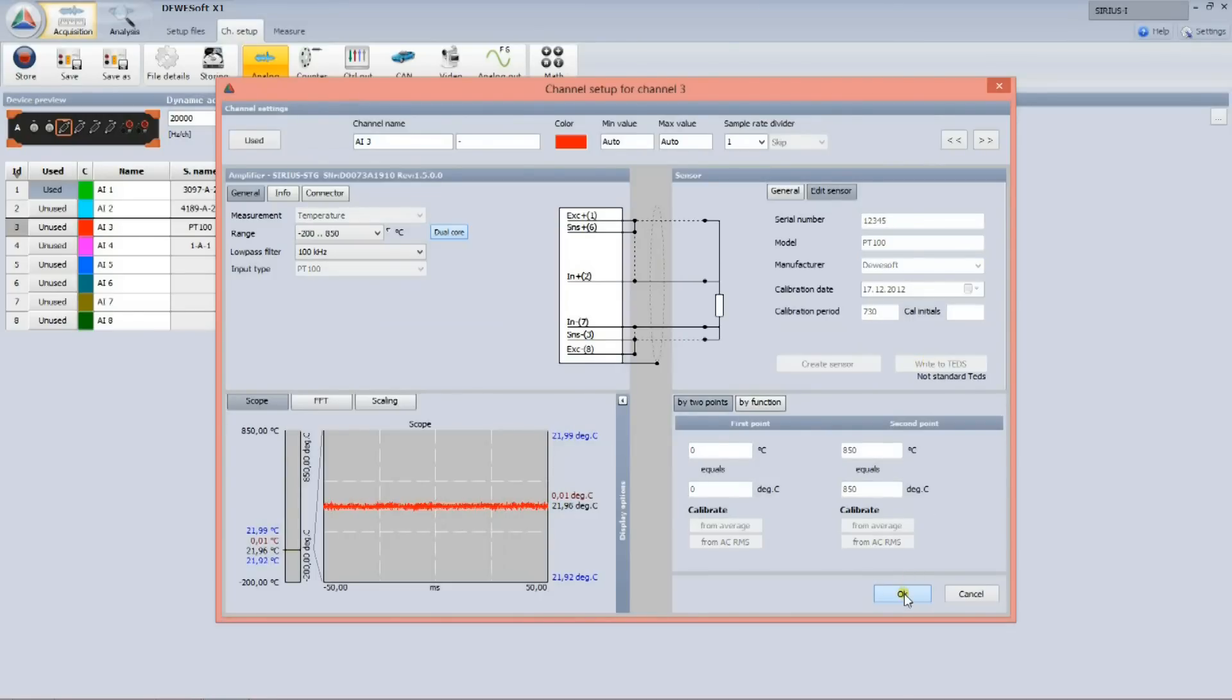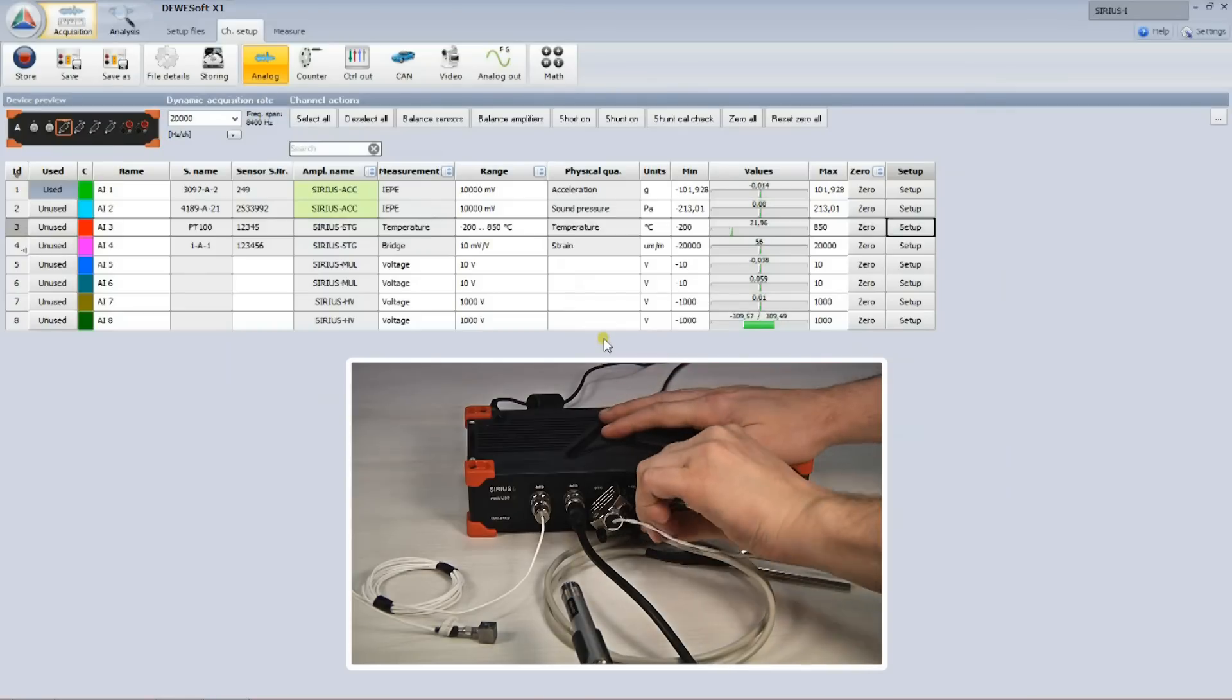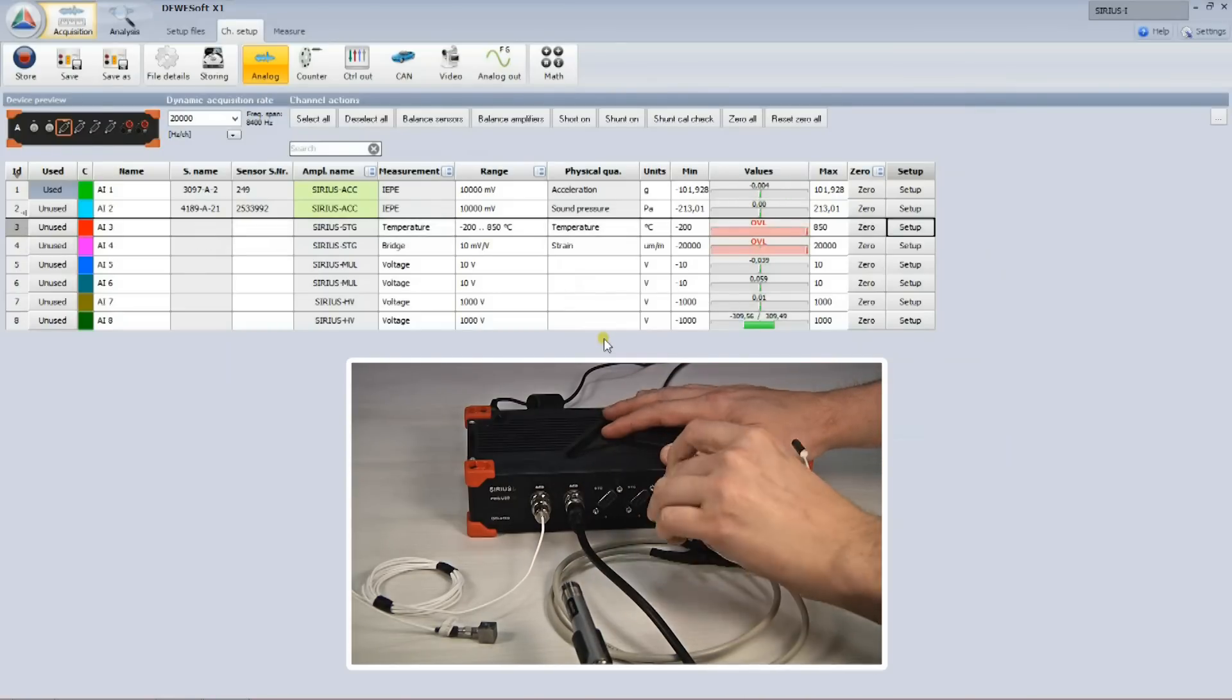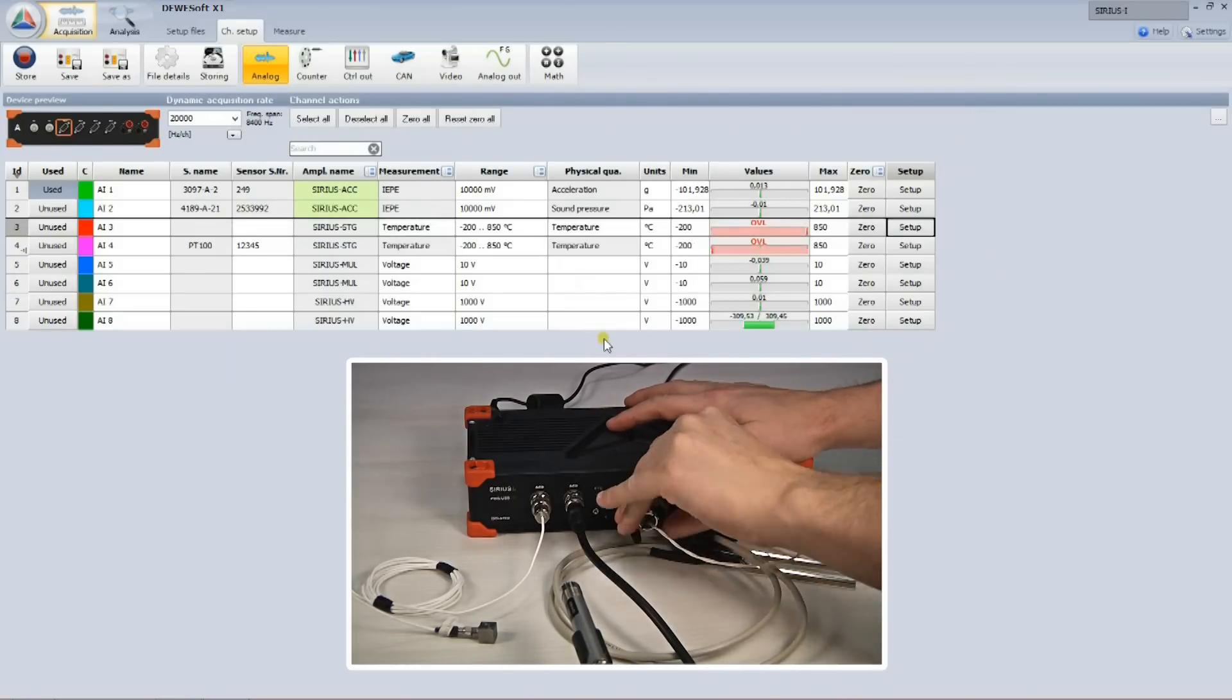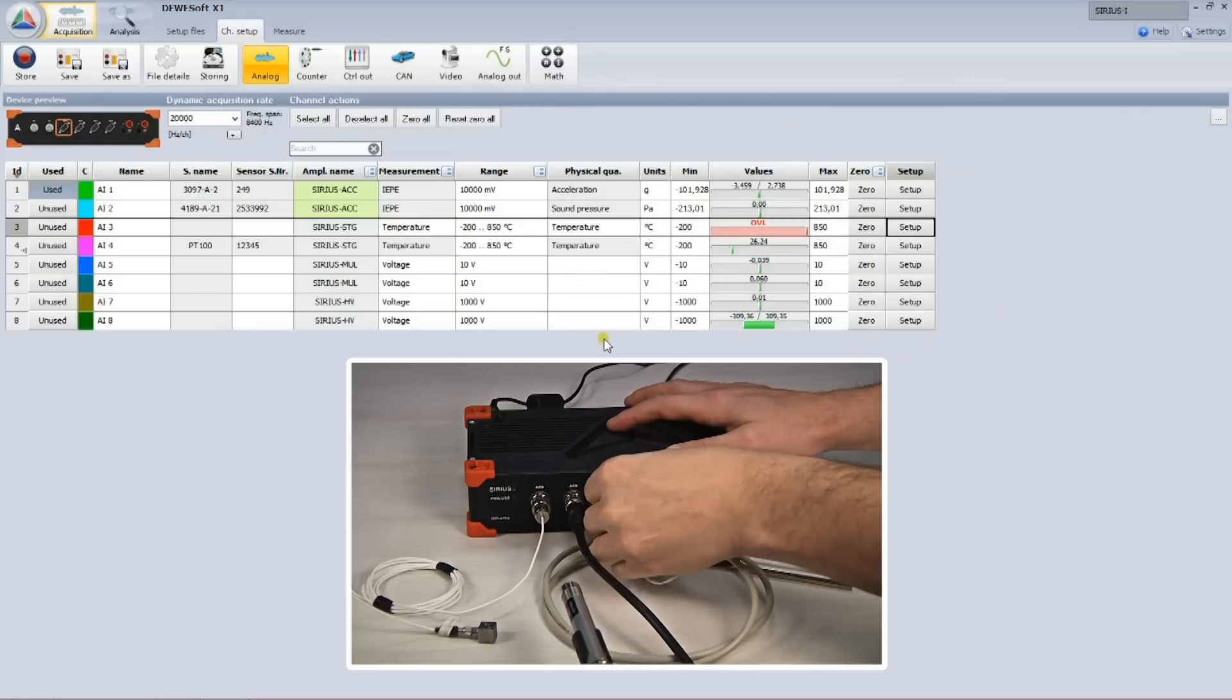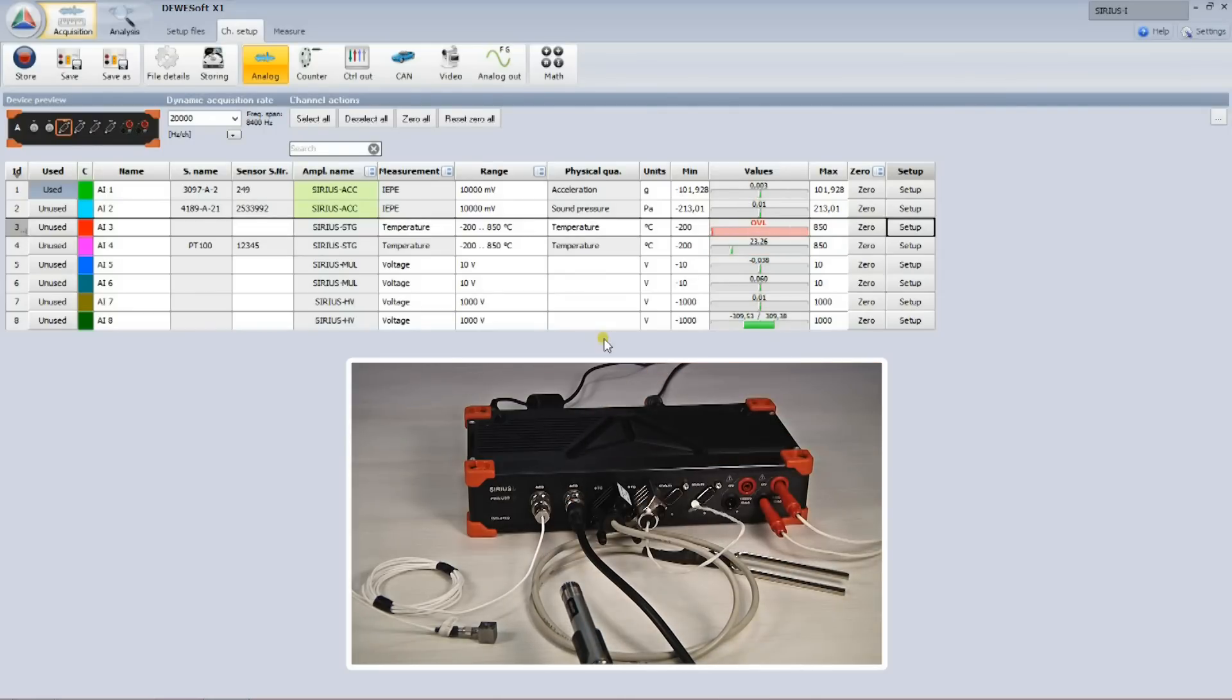Let's try to swap the sensors. By disconnecting the strain and temperature sensor and connecting them in the reverse order, I can see all the settings of the strain on channel 3 and the temperature sensor on channel 4.